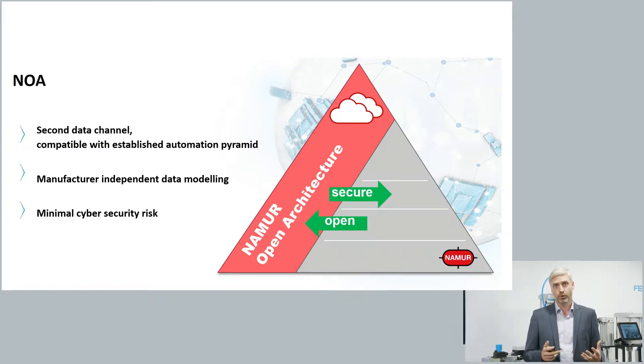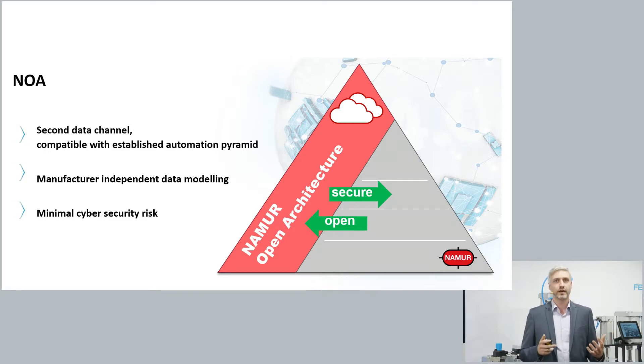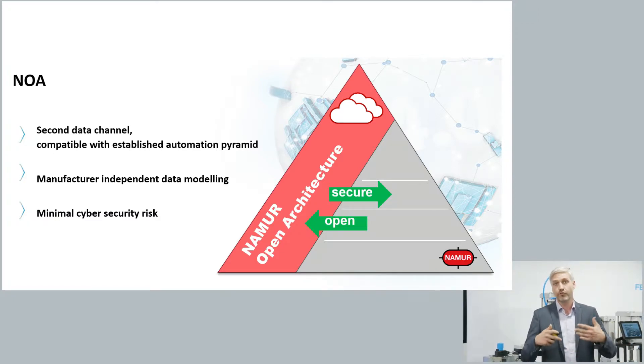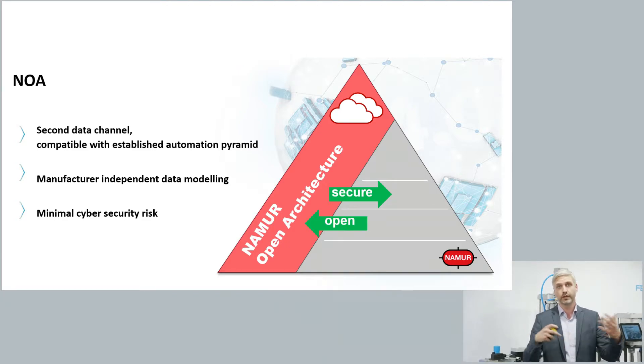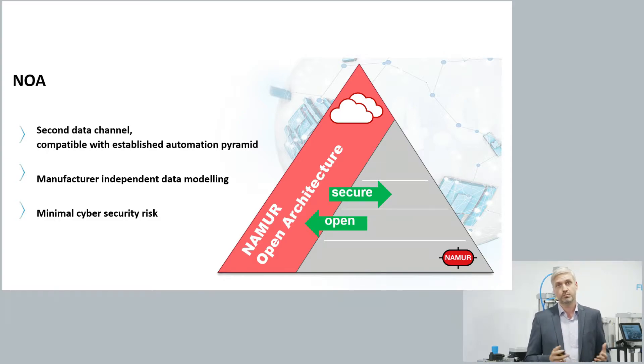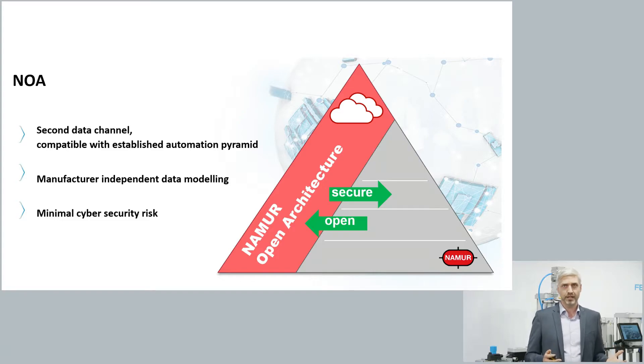The second important aspect of NOA is vendor-independent data modeling — a common language for your assets. A given class of assets needs to provide a standardized, specific set of data in a specific way, so you can easily compare data from one automation technology provider with another. Since plants typically have assets from many different vendors, this lets you compare them all in a unified, centralized view, bringing asset management to the next level.